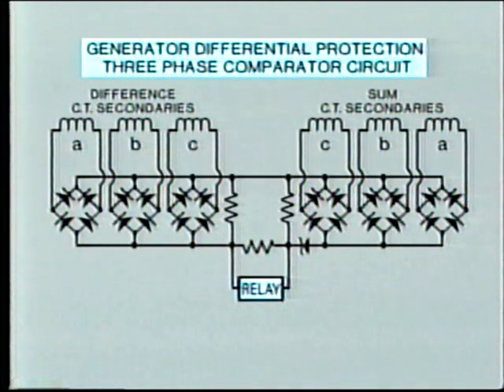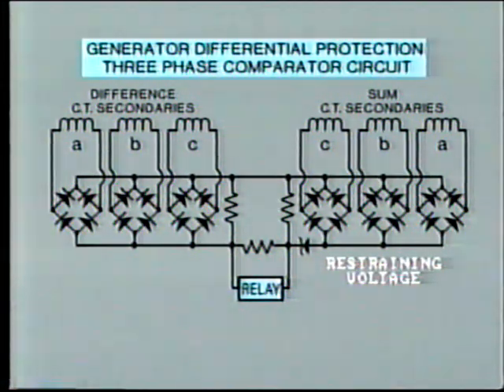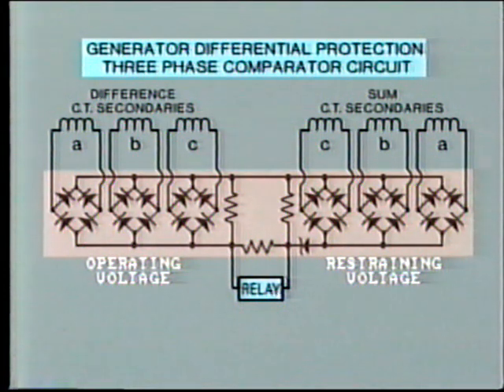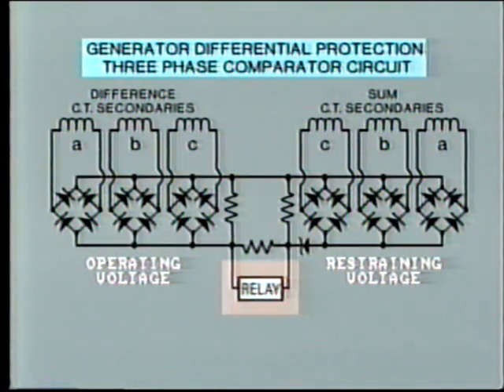These outputs are connected into the three-phase comparator circuit like this. The signals are rectified and the outputs from all three phases are paralleled. The restraining voltage on one side and differential voltage, that is the operating voltage, on the other. The output from this amplitude comparator is fed into this trip circuit, which is essentially the level detector that we examined earlier.